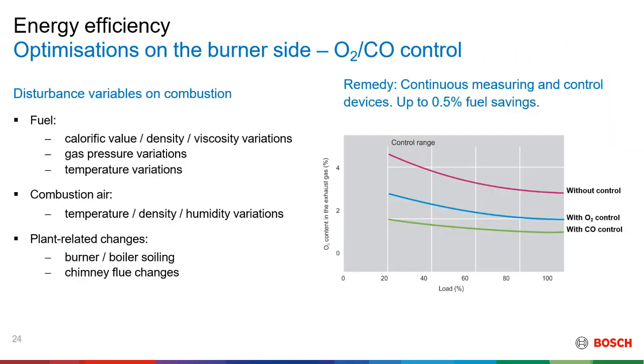Okay. So there are variances during combustion. The first one is the fuel, which can vary in calorific value, density, and viscosity. If it's gas, it can be the gas pressure, the ambient temperature, or the pressure of the fuel. The combustion air has different temperature, different density, different humidity levels. Then you have different burners having different efficiencies, and also we have flue gas challenges.